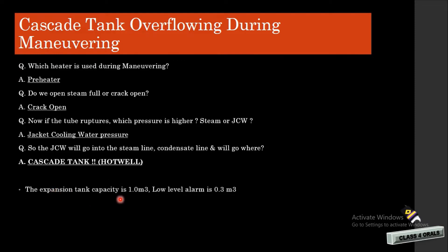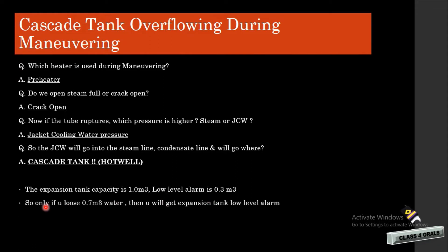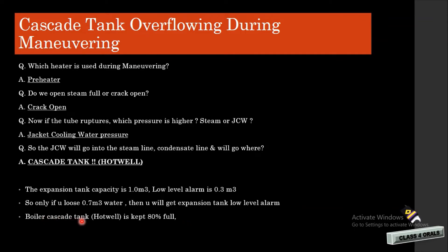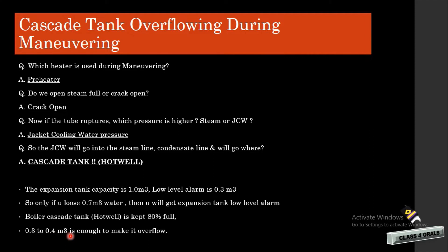The expansion tank capacity is approximately 1 cubic meter and its low level alarm is at 0.3 cubic meters. So if we are losing 0.7 cubic meters of water, we will get the expansion tank low level alarm. The boiler cascade tank or hot well is usually kept at 80% full, meaning 0.3 to 0.4 cubic meters of jacket cooling water is quite enough to make the cascade tank overflow. This is why the cascade tank overflows during maneuvering.